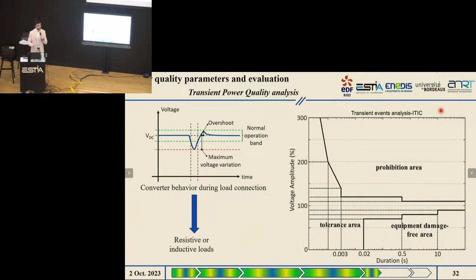And we could evaluate the behavior of our converter using already existing curves, such as the ITIC curve, which was developed in order to maintain a certain level of compatibility with electronic equipment. And what I'm trying to show you here with these figures are the results that were obtained when our DC grid was submitted to AC voltage variations, voltage dips or voltage swells, and to DC voltage variations. And we can see here that even for a 25% AC voltage dip that largely impacts our intermediary DC bus voltage, as you can see here in blue, the output DC voltage at the output of our converter is not very impacted, which means at the end that our control is capable of bringing the voltage back into acceptable time periods.